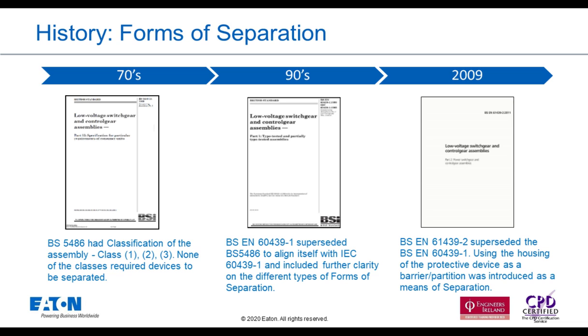So a little bit about the history. Going back about half a century, the standard for low voltage assemblies in the UK was BS 5486. At the time, regarding internal separation, we had the class of assembly. None of these classes required the functional device, so your protective device, to be separated. In the early 90s, the British standard aligned itself with the international standard, which gave birth to BS EN 60439.